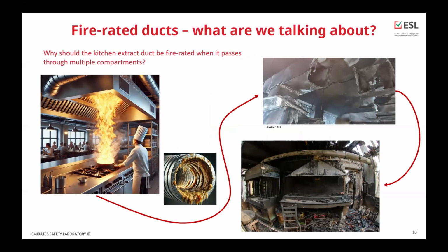So why these fires are happening is, as you can see here in the picture on the left side, maybe it's funny, but these represent a situation which is visible in most touristic places, where the kitchen makes the flame really high and really wide just to entertain their guests, the clients of the restaurants. Very often these flames are sucked in, pulled into the extraction system.